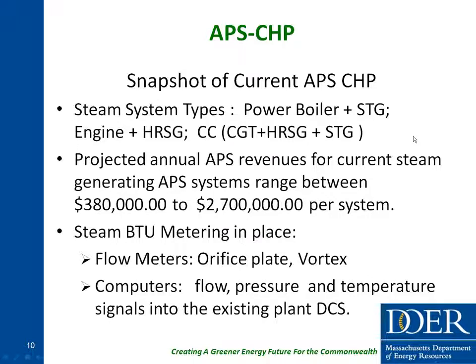The types of steam BTU technologies in place: flow meters, orifice plate, and I really should have called that DP because some of them are not orifice plates, some of them are Venturi, and vortex meters, and we also have one system with an Annubar flow meter. Computers: typically the flow, pressure, and temperature signals either go into an intermediate flow computer or directly into the existing plant distributed control system, which is then programmed to compute on a real-time basis and totalize the net energy, the net steam BTU. Next slide, please.